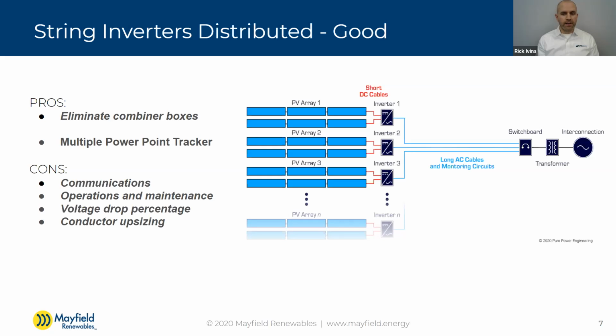Conductors are one of the more expensive items on a project that you can actually control. There's a lot of pieces as an engineer or designer that we can't change—we've got the inverter, but we can't really tweak the inverter or the panels or the switchboard. We could do minor things, but an area where we can really value engineer a system and put our own stamp on it is through conductor sizing, trying to figure out the best way to get the best bang for the buck when spending money on conductors, making sure that extra money pays for itself through reduced voltage drop. So it's an important area, and a fun one for our engineers to work on, because we really have flexibility in what we do.